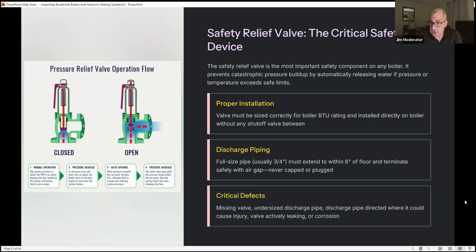So, proper installation. The valve must be sized correctly for the boiler BTU rating and installed directly on the boiler without any shutoff valve in between. Discharge piping: fully sized pipe, usually 3/4, must extend within 6 inches of the floor and terminate safely with an air gap, never capped or plugged. Critical defects: missing valve, undersized discharge, discharge pipe pointed where it could cause injury, valve actively leaking, or corrosion.